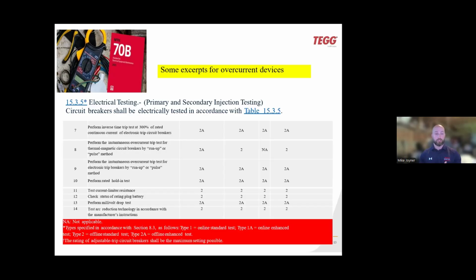When I was in the field, primary injection testing, for lack of better terms, was in my mind always a destructive test, especially for older equipment. Newer equipment actually does require it, like newer Eaton or Siemens equipment, once every 5 years. But for the most part, what you're doing is putting 300% of continuous load into the actual breaker itself. If the breaker's not rated for it, or if it causes any kind of fault, and you don't have a backup breaker, the breaker's going to fail and you may be out of luck. So we tend to stay away from primary injection testing unless it's manufacturer spec for the newer equipment.